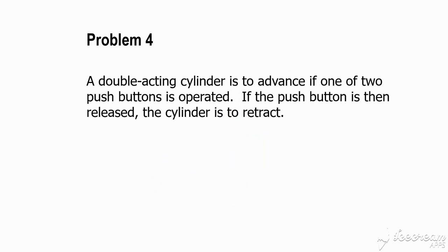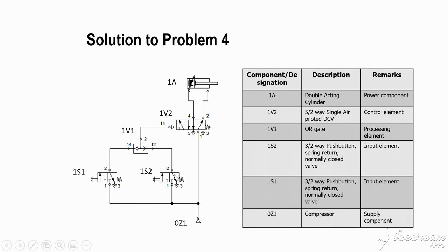Problem 4: A double acting cylinder advances if any one of two push buttons is operated; when the push button is released, the cylinder retracts. Since either push button should work, an OR gate valve is required. Two push buttons (1S1 and 1S2) feed into an OR gate valve (1V1). When either push button is pressed, the signal passes through the OR gate to activate the 5x2 valve and extend the double acting cylinder.